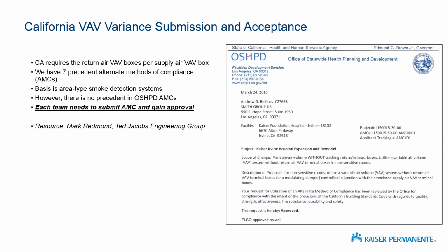The basic idea of the write-up is that if you have an area type smoke detection system, then less than perfect balances between supply and return air in the rooms don't matter much to smoke spread because the fan shuts down quite quickly. So that's how we've gotten it approved. However, when it comes to OSHPD, there is no such thing as precedent. So every design team and every project needs to develop the AMC, submit the AMC, and get it approved.